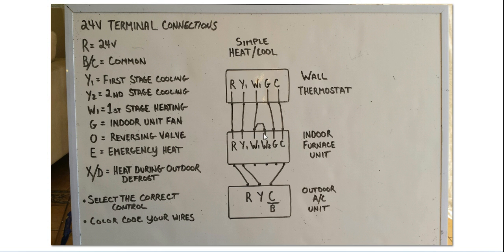I've linked this to the W2 because depending on what kind of indoor furnace you have, sometimes it has different stages of heat. And a lot of times, you can either get a two-stage heating thermostat. Some people don't. They just link it. So it just links over. So when your heat comes on, both stages come on. It all depends on what you want to do when you're hooking it up.